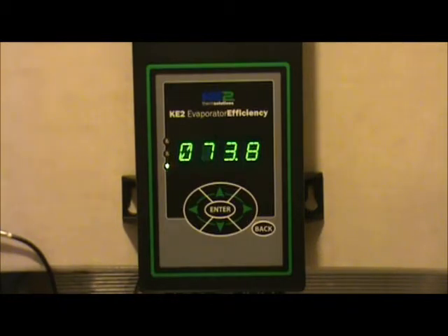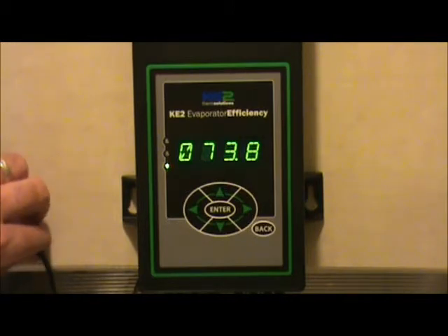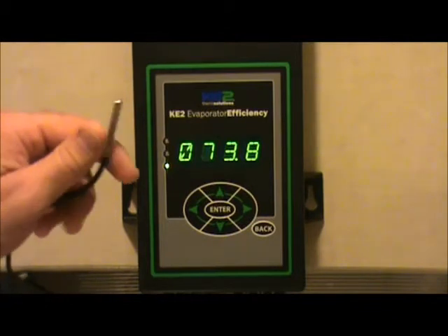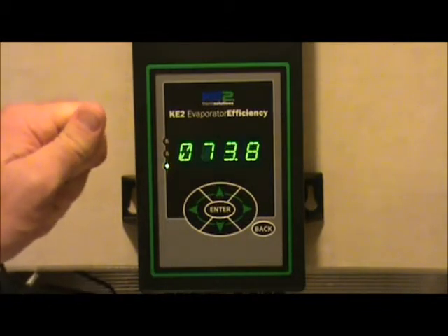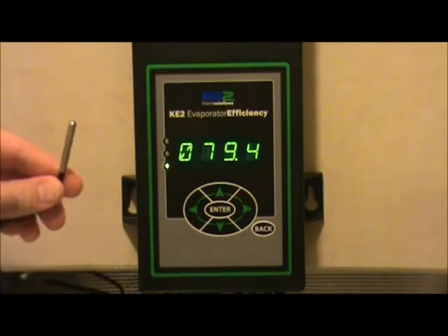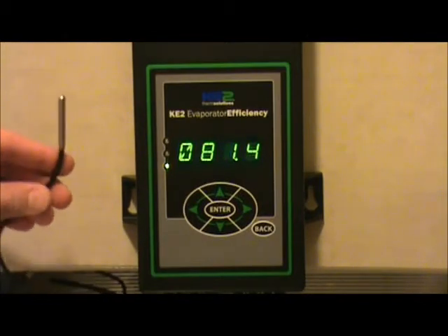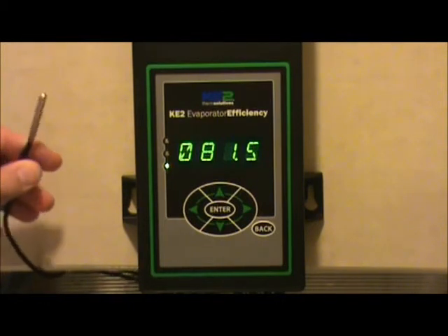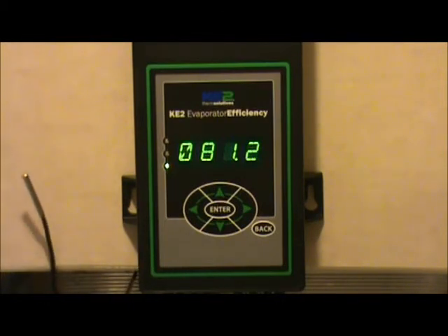Also, during the installation process, once you've installed the temperature sensors, to verify that you have the air temperature sensor installed in the air stream in the right place, and the coil sensor in the coil, the quick and easy thing to do is to grab the air temperature sensor and hold on to it. You should see the readout on the display increase, obviously, in temperature as you touch it. That way you can ensure that you do have the proper sensor in the proper location, as far as the air sensor in the airstream, the coil sensor on the coil.